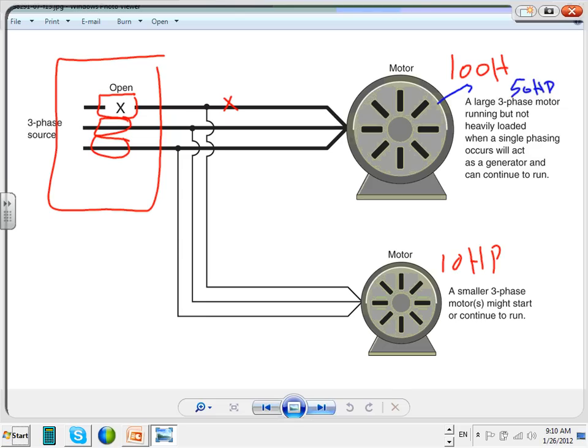But at a higher amp though, at a higher amp. And if you don't have overload protection, they will burn. So that's where these bigger generators come in. If you get into a building where we have a 100, remember the difference: the 100 guy, when it's running half loaded, will generate enough induced voltage into the last phase for this baby not just to keep running, but to even start. If there was a stop, to start even, or continue to run.